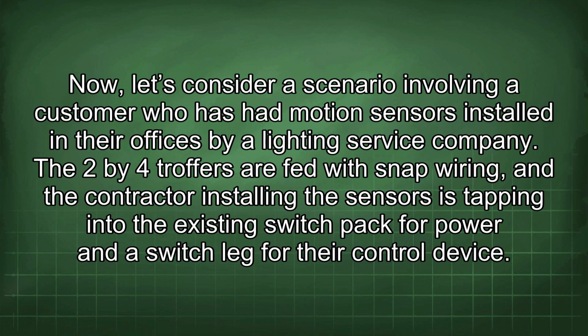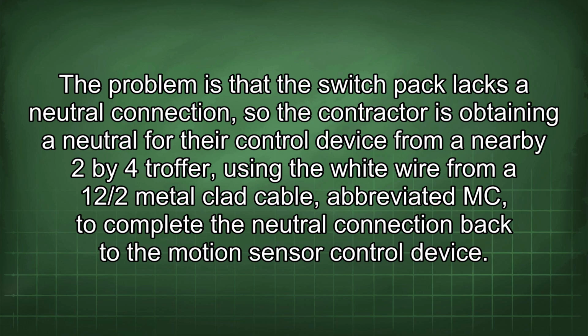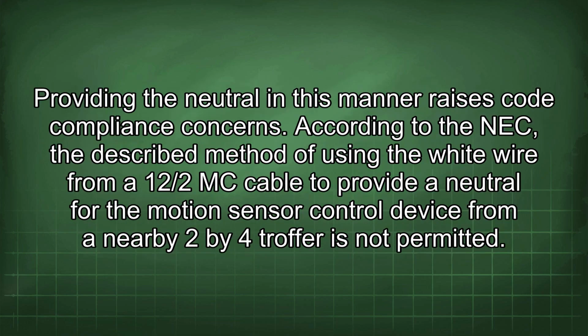Now, let's consider a scenario involving a customer who has had motion sensors installed in their offices by a lighting service company. The 2x4 troffers are fed with snap wiring, and the contractor installing the sensors is tapping into the existing switch pack for power and a switch leg for their control device. The problem is that the switch pack lacks a neutral connection, so the contractor is obtaining a neutral for their control device from a nearby 2x4 troffer, using the white wire from a 12/2 metal-clad cable, abbreviated MC, to complete the neutral connection back to the motion sensor control device. Providing the neutral in this manner raises code compliance concerns.